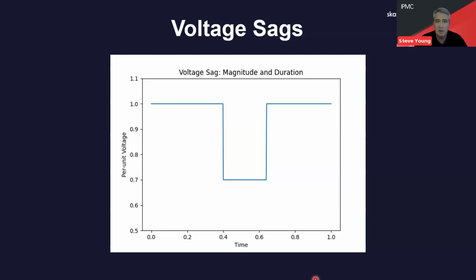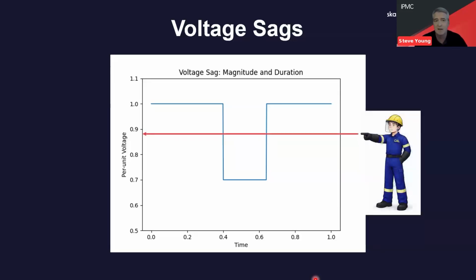Now, we learned about the heavyweight champion, if you like, in that voltage sags are probably the most troublesome characteristic that we have to deal with. So if you look at these characteristics there, we've got time along the horizontal axis, and we've got magnitude on the vertical axis. So by measuring both the magnitude and duration, and perhaps cross-referencing that with the low limit that's tolerated by the connected loads, we know that the magnitude and duration then define the impact on the equipment.